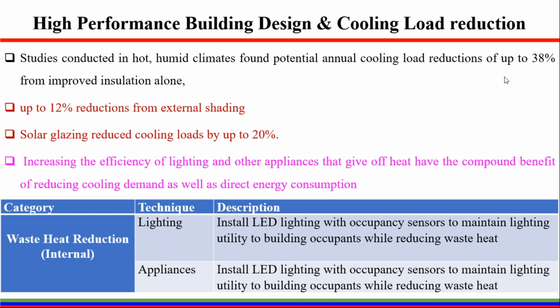Studies conducted in hot and humid climates found a potential annual cooling load reduction of up to 38% for insulation. It means that if you can improve the insulation of the rooms that you need to condition, you can reduce the overall cooling load by up to 38%. If there's external shading, 12% can be reduced. Solar glazing can reduce up to 20%. So these are the measures that can be taken to reduce the overall cooling load.